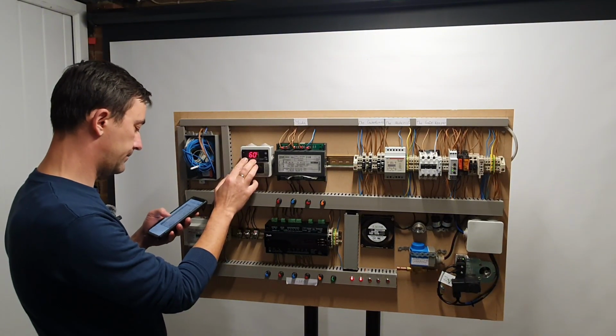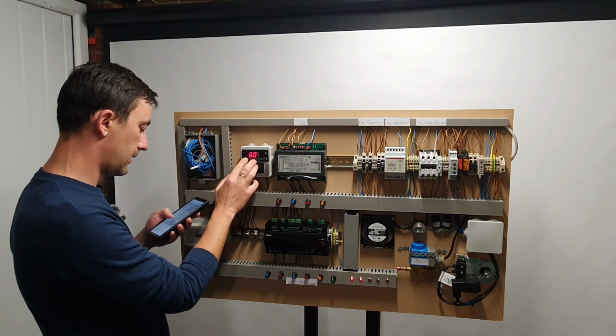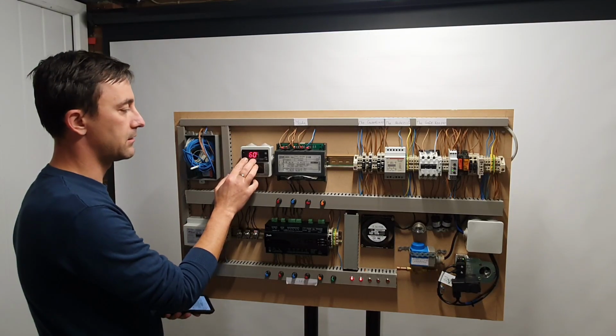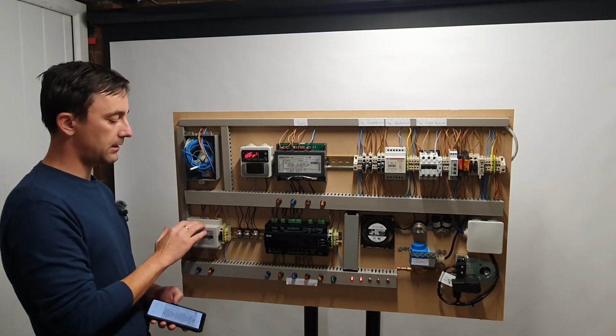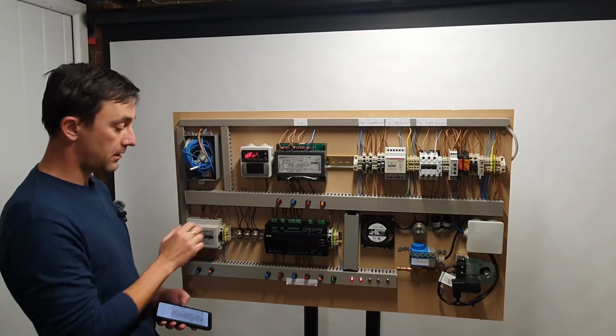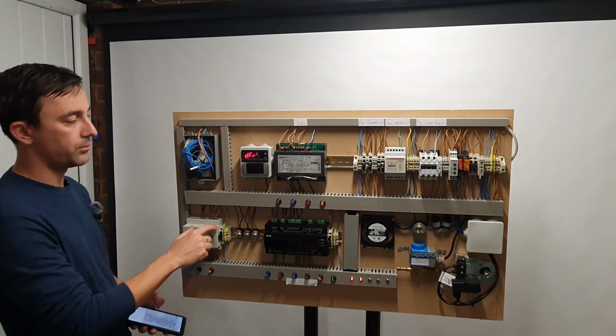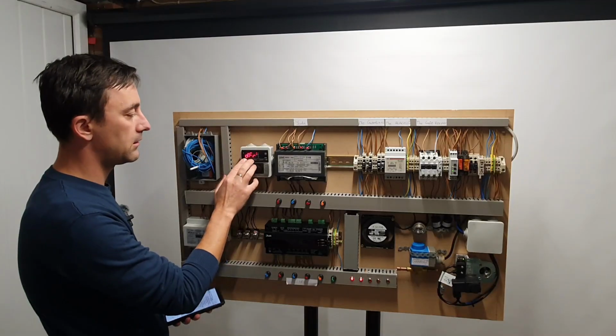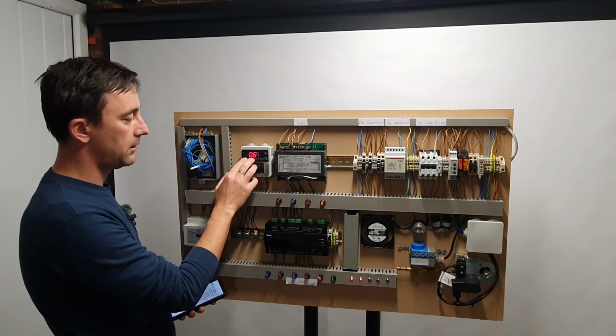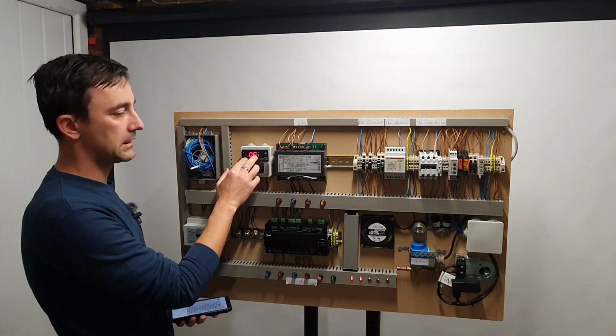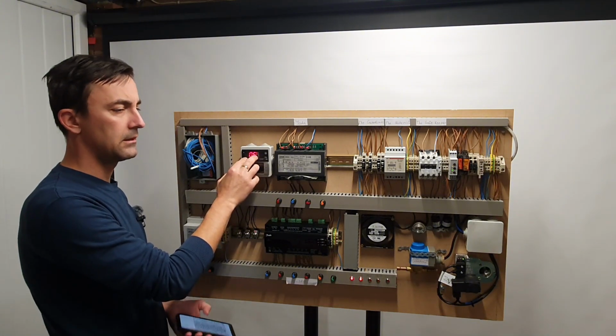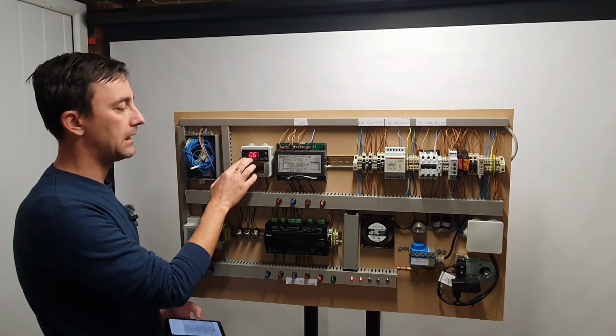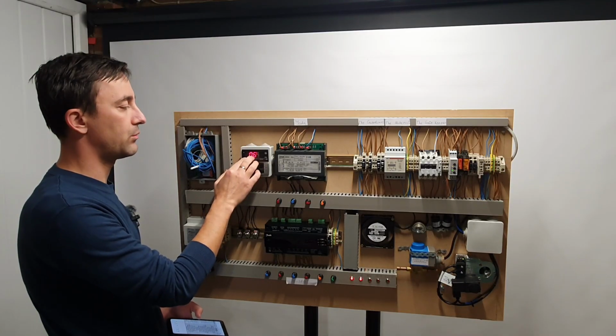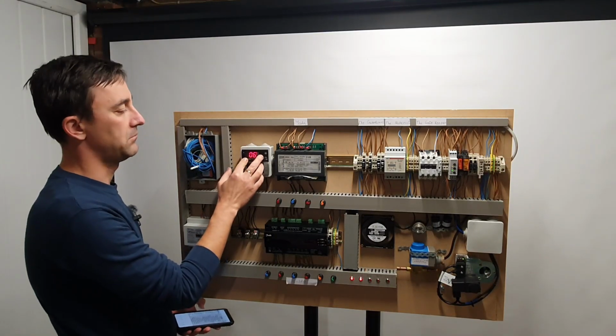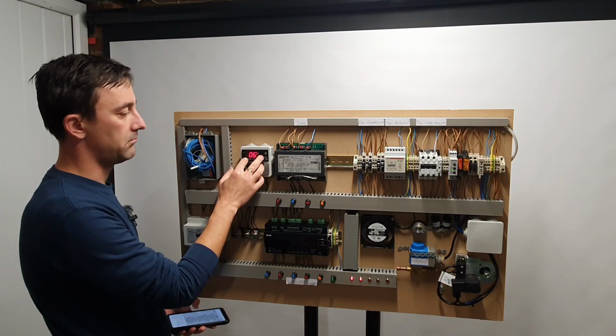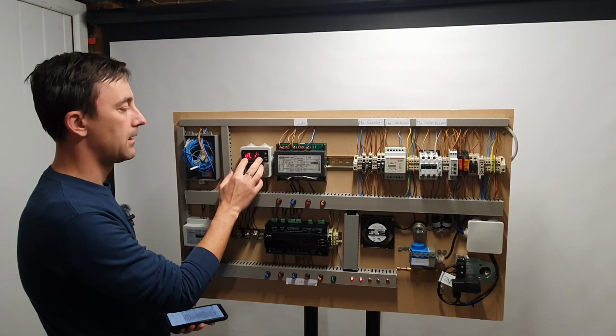2CD is start delay of the second compressor. Well, this controller does not have that option. Even though the parameter is there, you don't have the output here. So we're gonna ignore that. Defrost, that's the defrost interval. So it's every 6 hours for a freezer. I think it's okay. It depends on what the client wants, or maybe what the commissioning sheet says. Every 6 hours, it's about right.